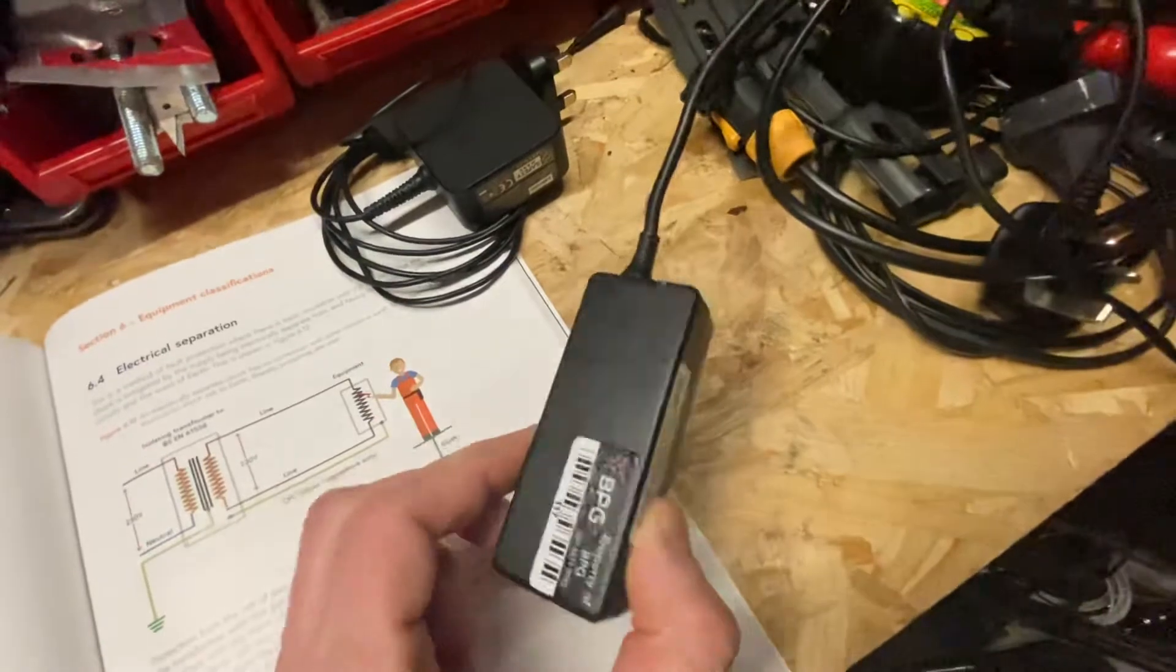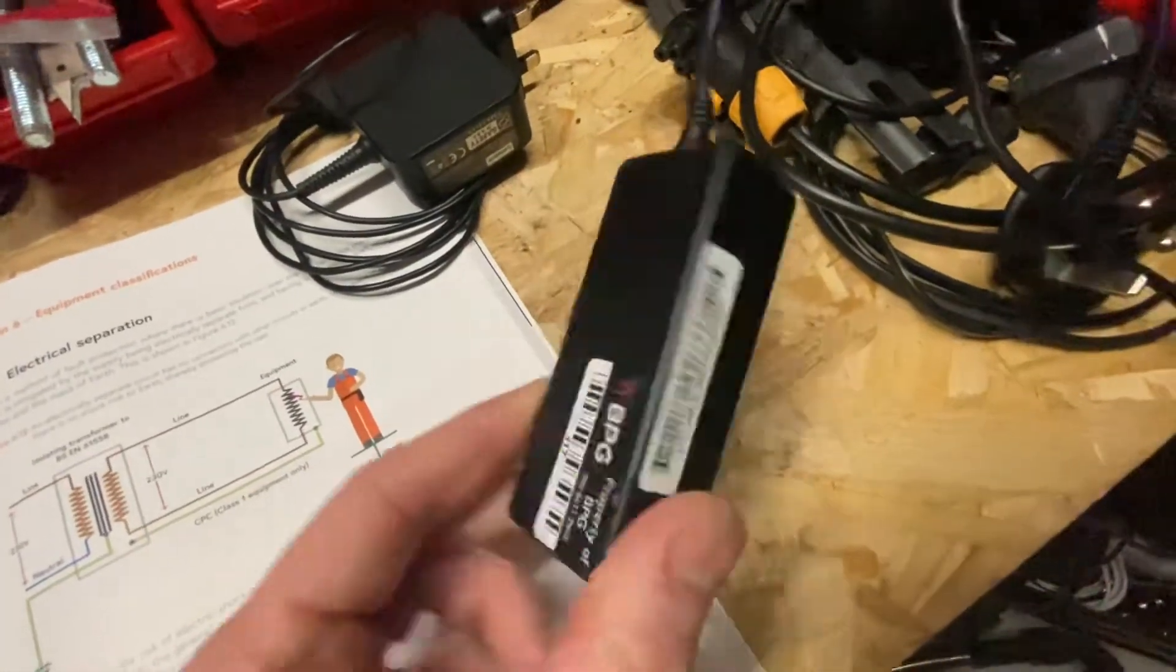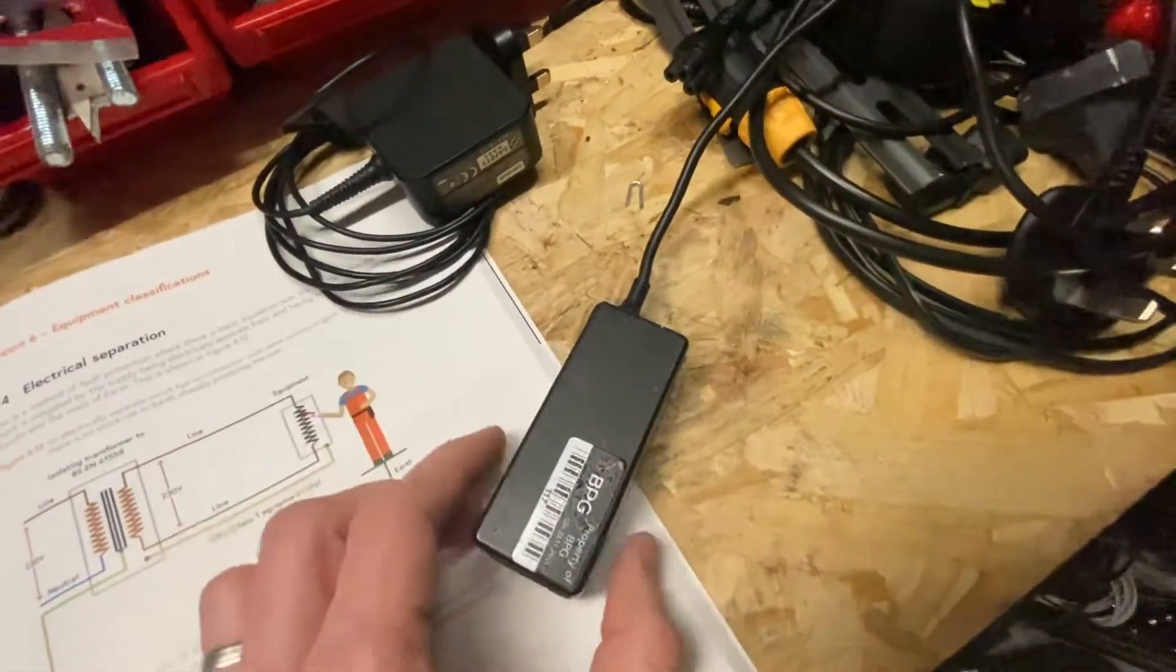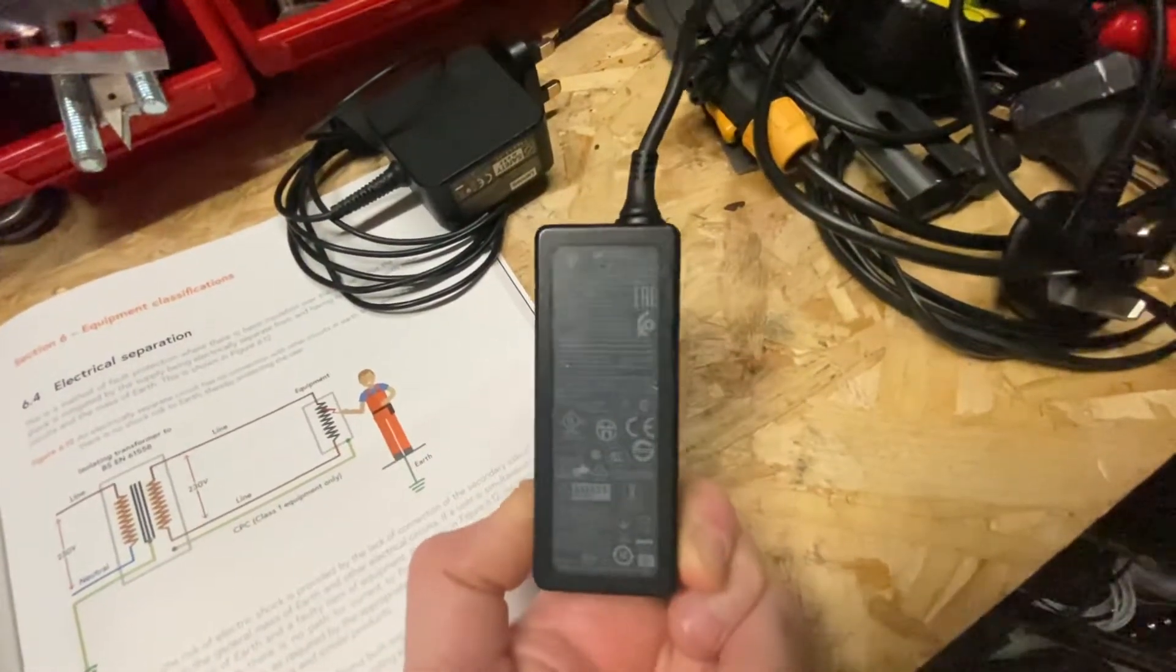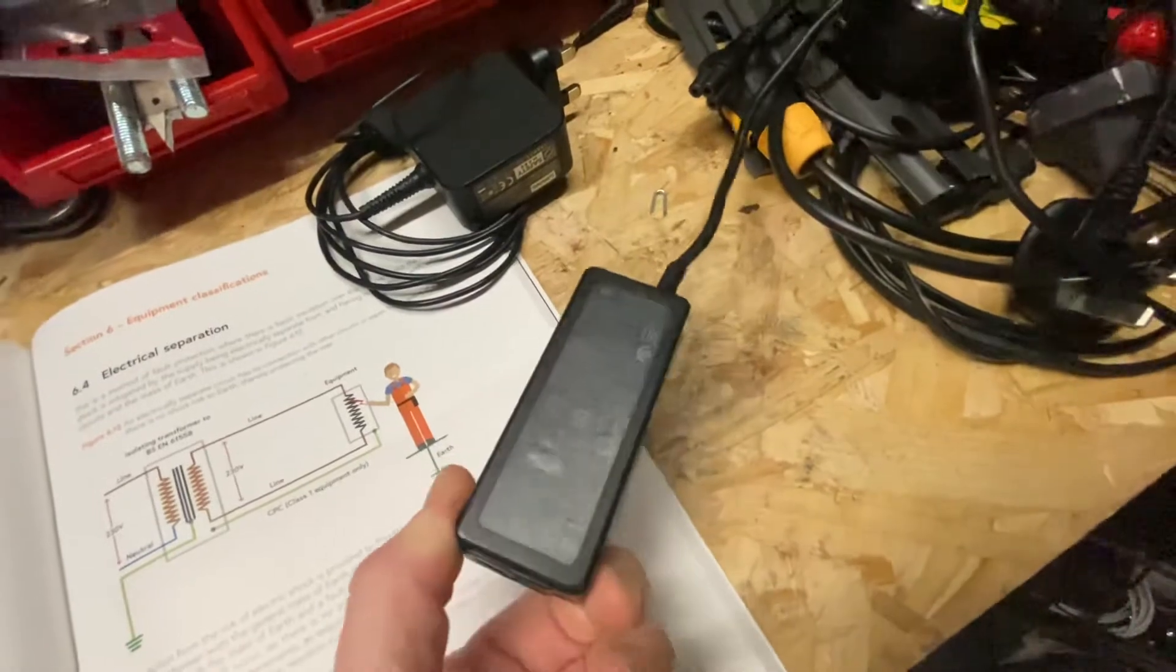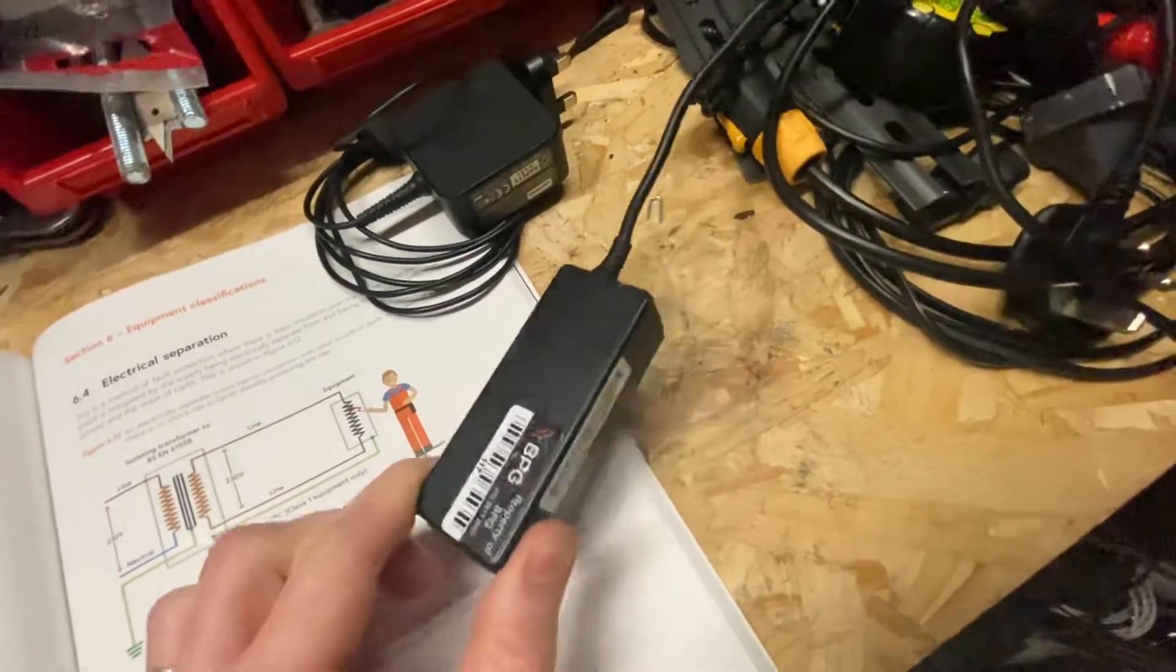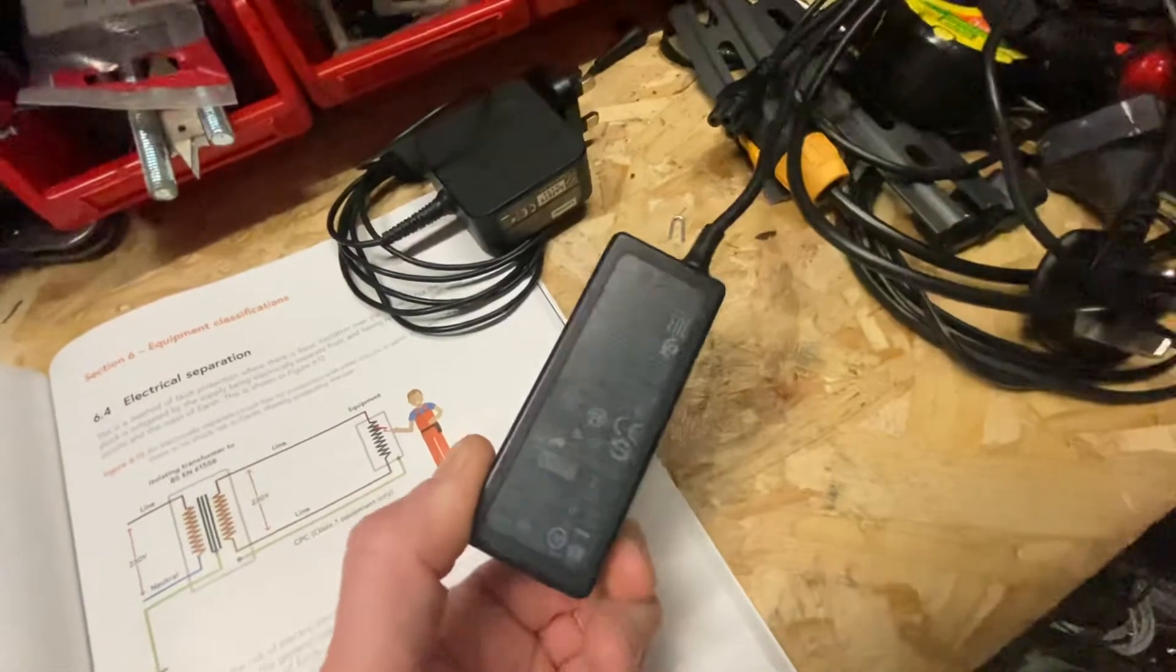But either way, if you treat it as a class 2 appliance, there's no external metal parts. So then you can't do any functional checks through your PAT testing machine. The only check you can do is a visual check.